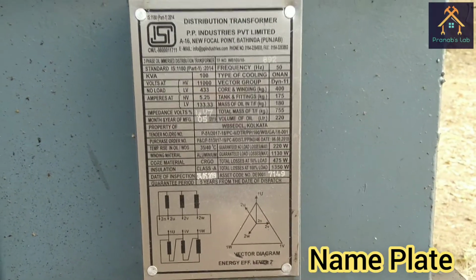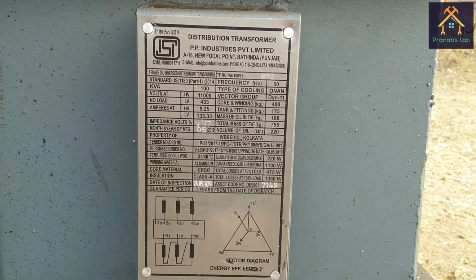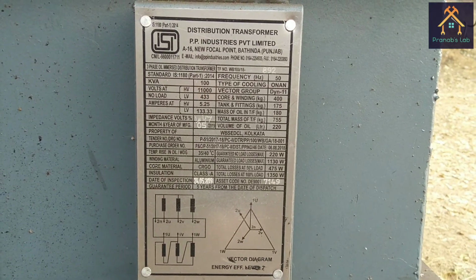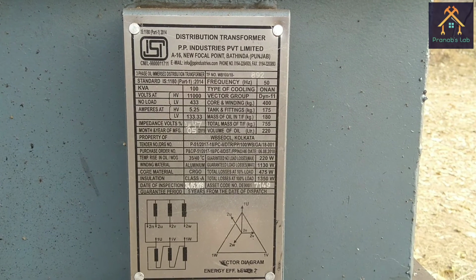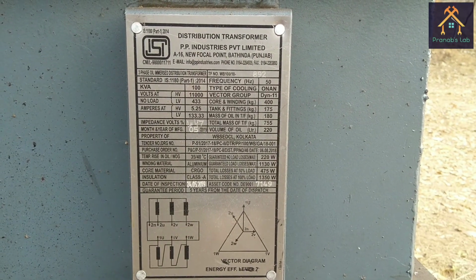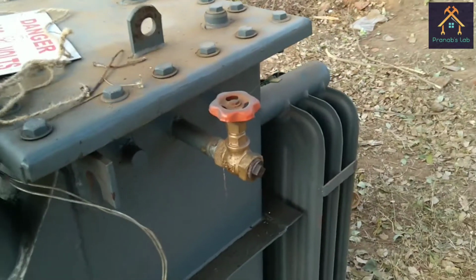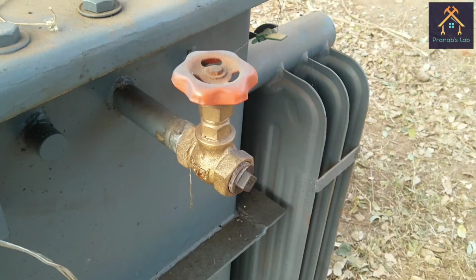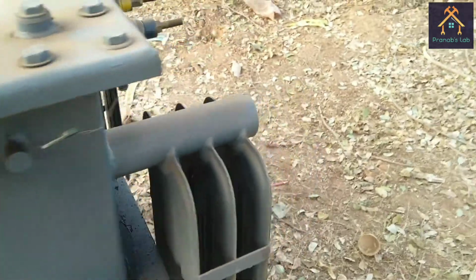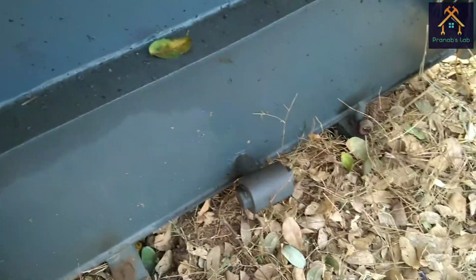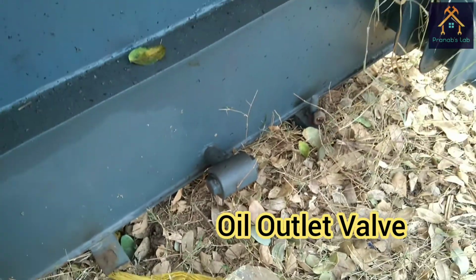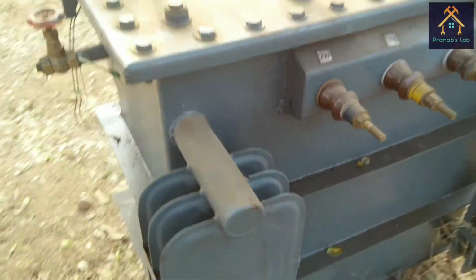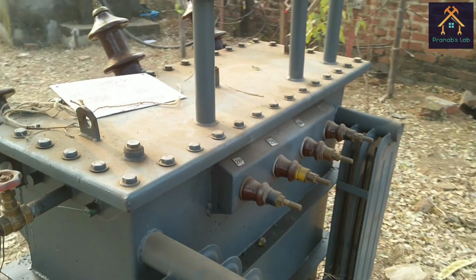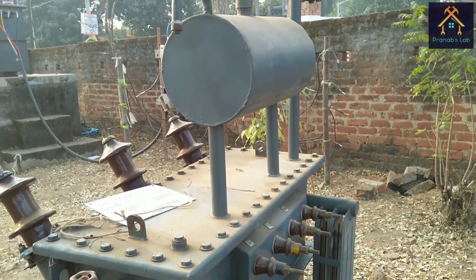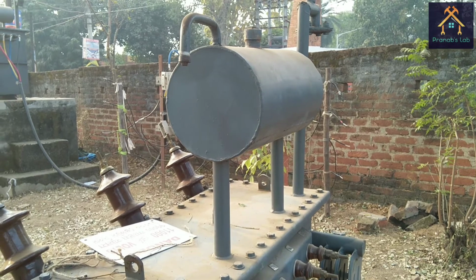Now you can see this is the nameplate of the transformer. The full details of the transformer, that is the voltage rating, kVA rating, current rating, vector grouping and others are punched on it. I will discuss the nameplate with full details in another video. And you can see this is the transformer oil inlet valve. It is used to fill the transformer oil into the tank, and this is the oil outlet valve used to empty the tank. There should be 2 more vital parts of the transformer which are not fitted with it, that is the rod gap surge diverter and breather.